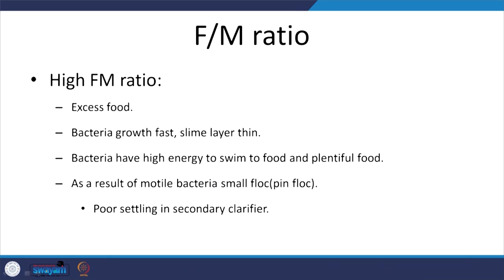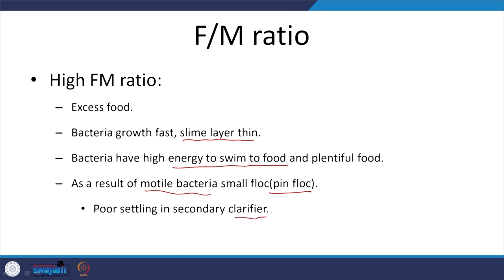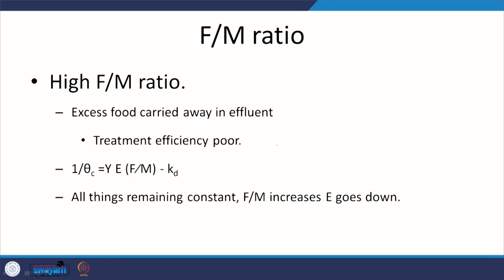With high F/M ratio — high food — bacteria grow fast, the slime layer is thin. We are talking about the exponential growth phase here. Motile bacteria have high energy to swim to food, forming pin flocs with poor settling. Additionally, high food means excess food is carried away and treatment efficiency is poor.